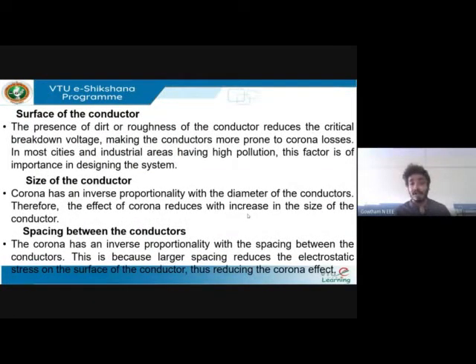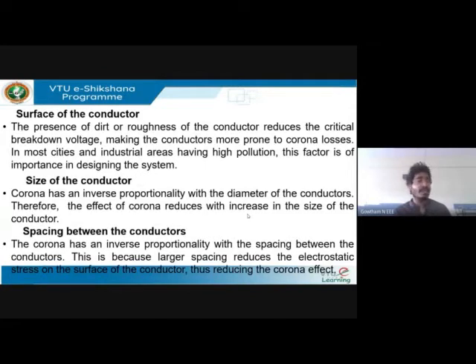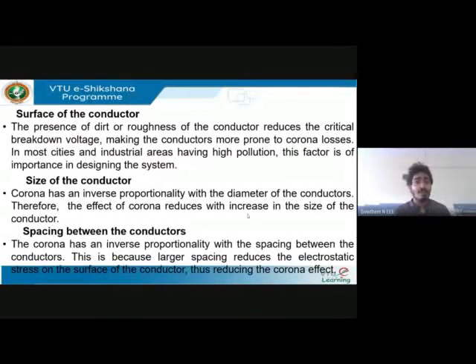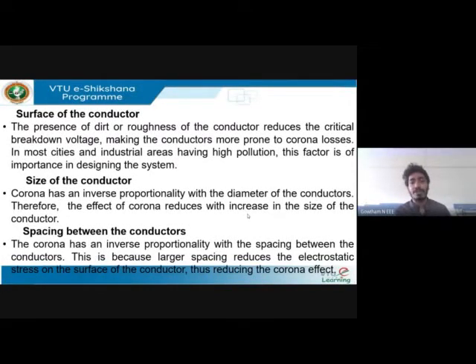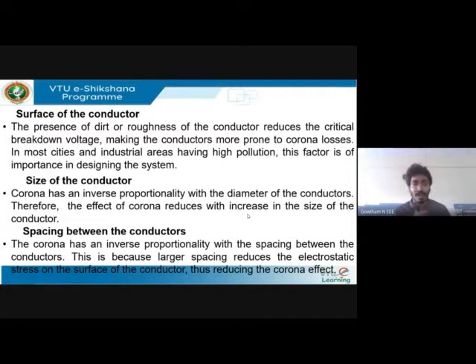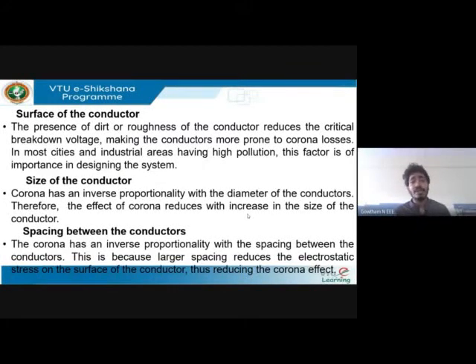Regarding surface of the conductor: if it is polished and smooth, the effect will be less; if it is rough, the effect will be more. The presence of dirt or roughness reduces the critical breakdown voltage, making the conductors more exposed to corona. In areas of high pollution, if conductor surfaces are not smooth, the effect of corona will obviously increase. We should consider the conductor surface when intending to reduce corona.